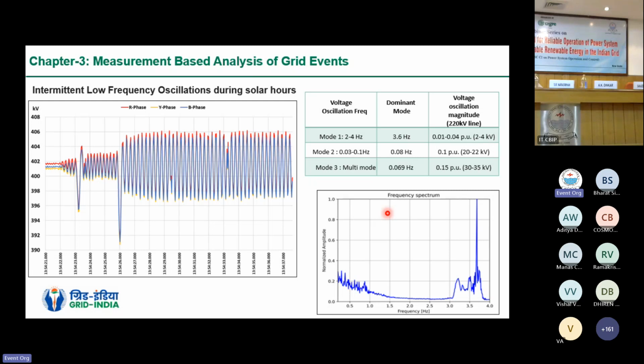The voltage oscillation magnitude can give an indication of the severity of this oscillation. Any power system, it is very difficult to operate with voltage oscillations varying from 20 to 35 kV of magnitude. So it is very important that the source of these oscillations is identified and mitigation measures are taken.